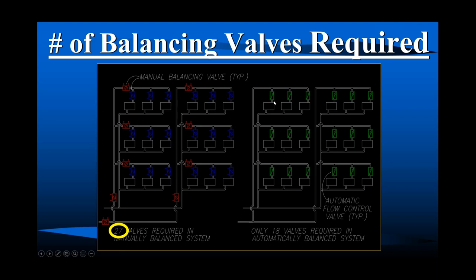If you use automatic flow balancing valves, this is cut from the factory for 3. We don't have to make 9 go here first. This is going to push back. It's got a spring in it. So 3, 3, and 3. Don't have to put one on the runout, nor the riser, nor the trunk split. There's only 18 valves in an automatic flow balancing valve system. And that's a big deal, because if we take a look at system versus system, the advantage price-wise changes dramatically. We have to do it right, though.